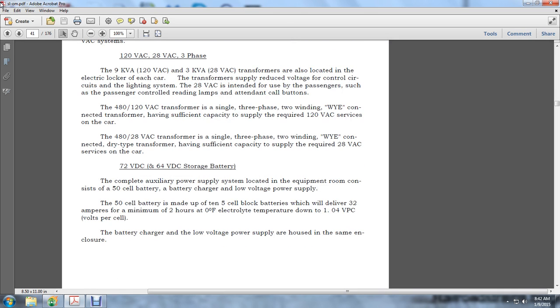72 VDC and 64 VDC storage battery. The auxiliary power supply is located in the equipment room. It consists of the 50-cell battery and a battery charger low voltage power supply. The 50-cell battery is made up of 5-cell block batteries, delivering a minimum of 32 amperes for 2 hours at 0 degrees Fahrenheit electrolyte temperature, down to 1.04 volts per cell.